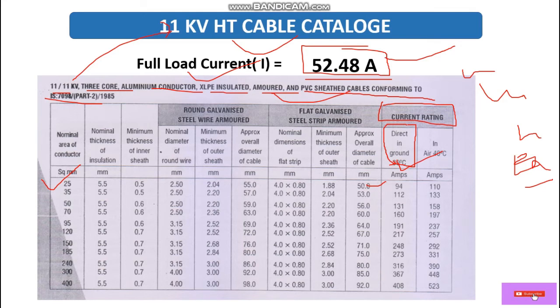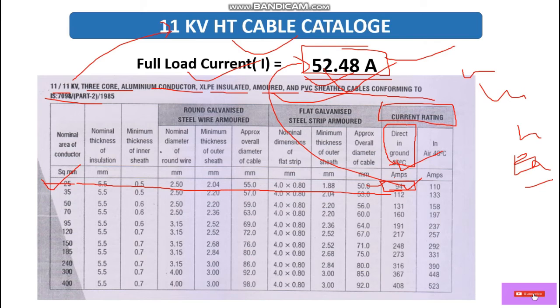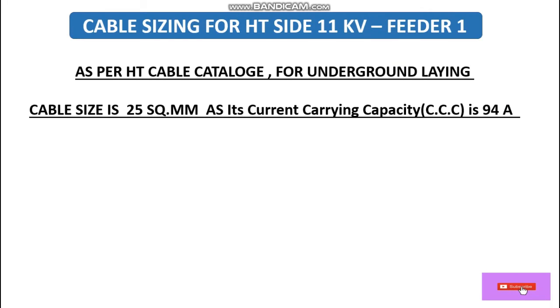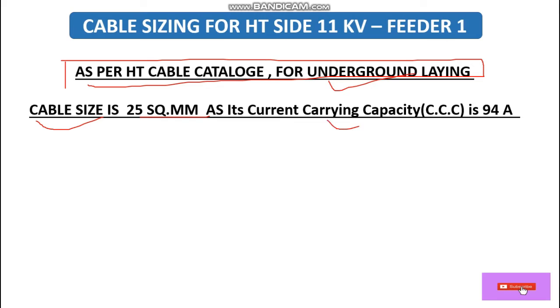For underground installation, a 25 sq mm cable can carry 94 amperes. That means the current carrying capacity of a 3-core aluminium XLPE 25 sq mm cable laid underground is 94 A. As per the HT cable catalogue for underground laying, the cable size selected is 25 sq mm aluminium conductor, 3-core, with a current carrying capacity of 94 amperes.